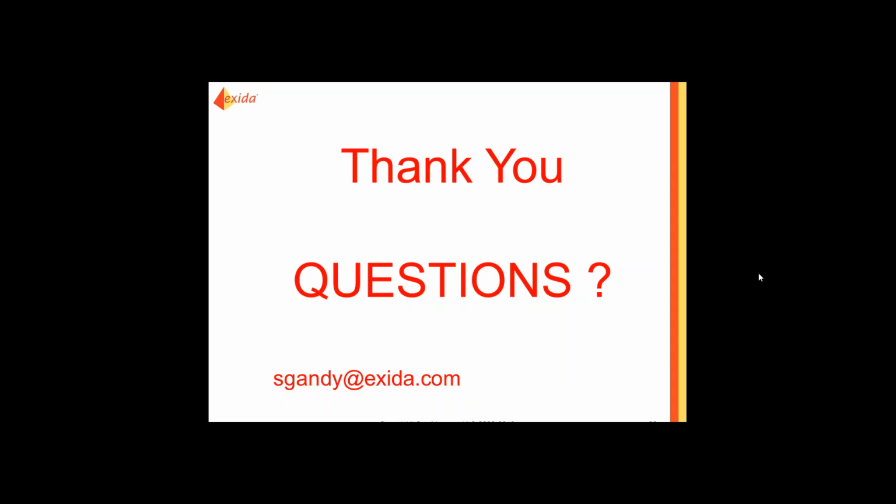Here again, you can use the SAEL list on our exida website, which has all certified equipment under different categories, not just the ones we've certified, but ones certified by other agencies. If we believe the numbers, we put them on our website. Then you have to do the calculation for each piece of equipment, because there are 3 barriers you have to overcome to meet the SIL level. One is the PFD average if it's a demand mode, or the PFH if it's continuous. The second is the hardware fault tolerance, and the third is the systematic integrity. The standard defines what you need to do there in terms of requirements.